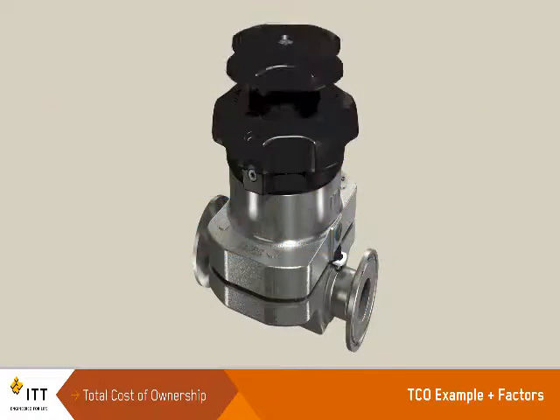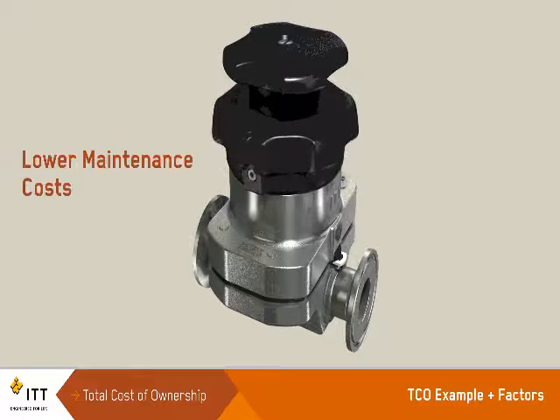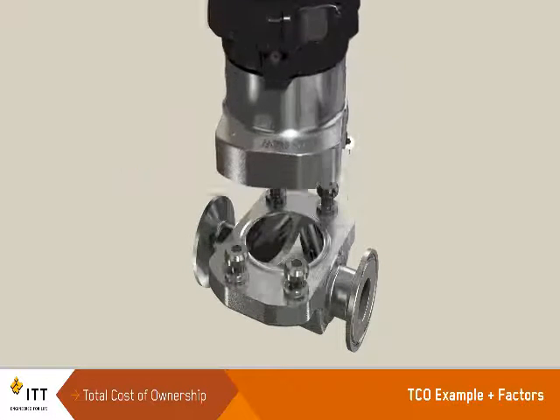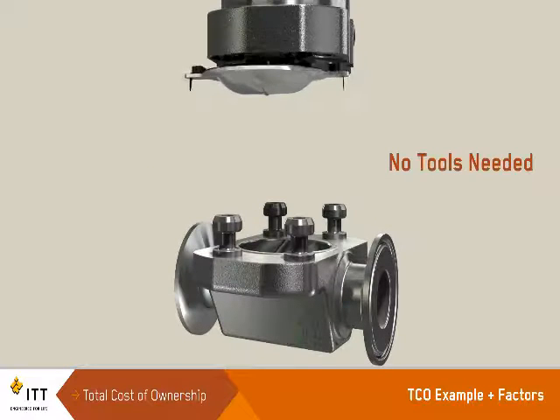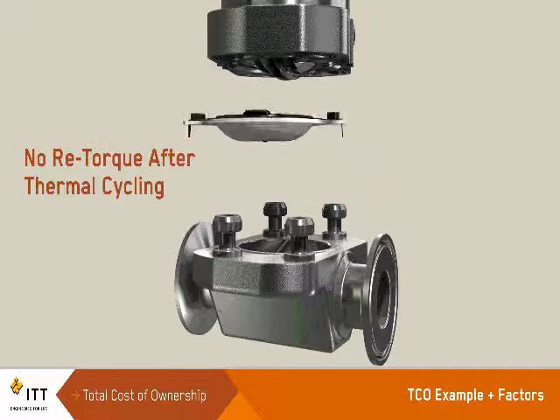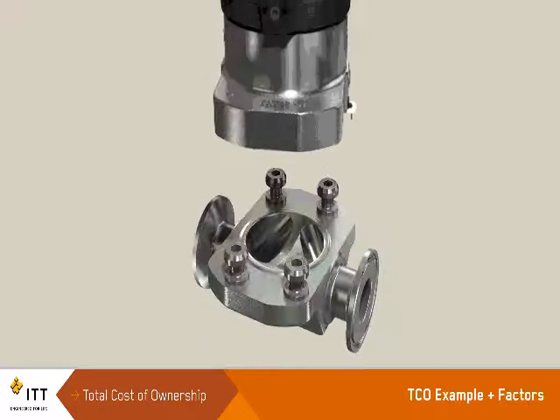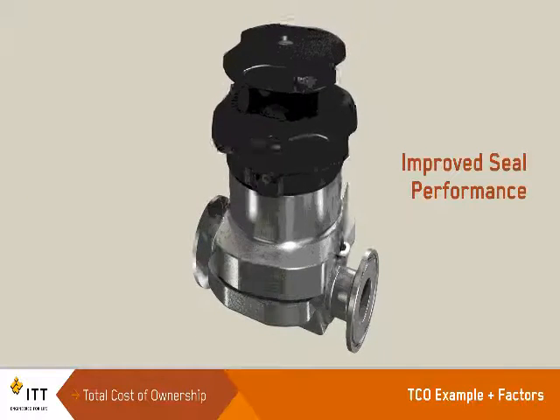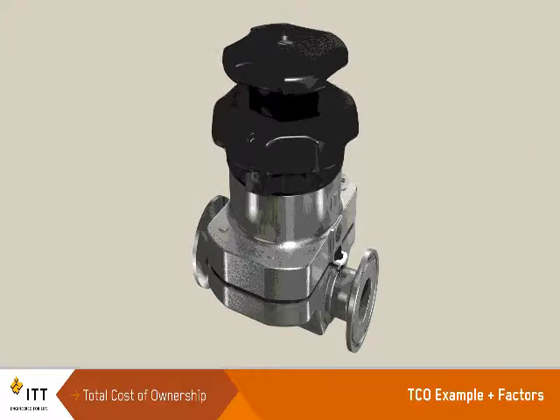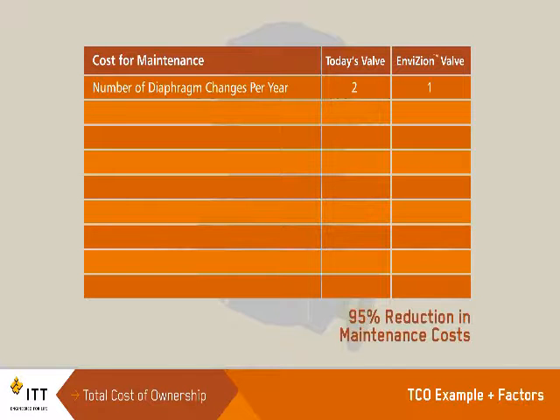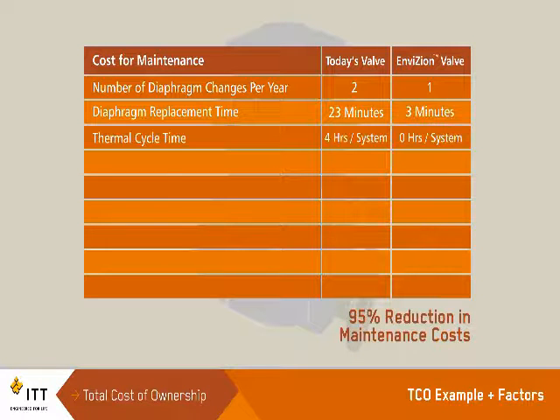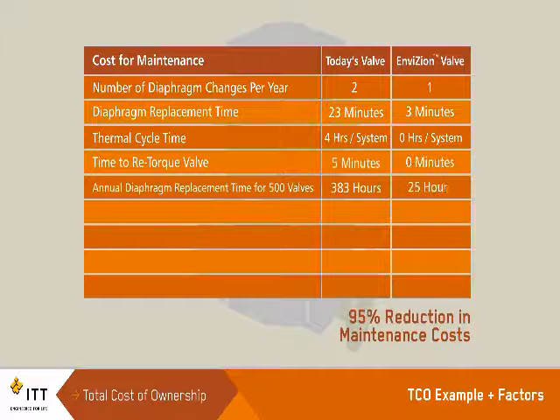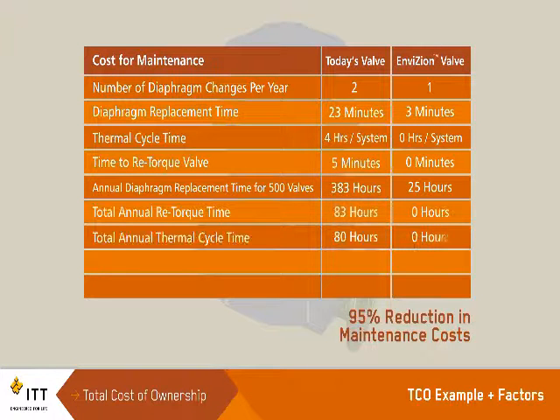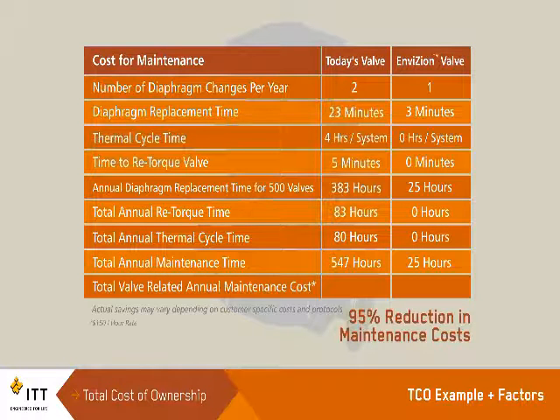Maintenance costs are lower because diaphragms are faster and easier to replace. No special torque procedures or tools are needed. And after thermal cycling, no retorque is required to ensure a proper seal. The cold flow control consistently improves seal performance, which means diaphragm life can be predicted and preventive maintenance intervals can be extended. For example, in a 500-valve biopharm manufacturing facility, the Pure-Flo EnviZion will substantially reduce maintenance labor, time, and cost. Total maintenance hours are reduced by 522 hours, and maintenance cost by more than $78,000.